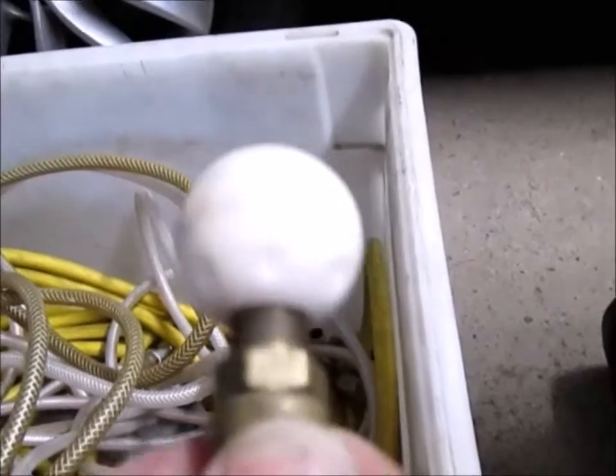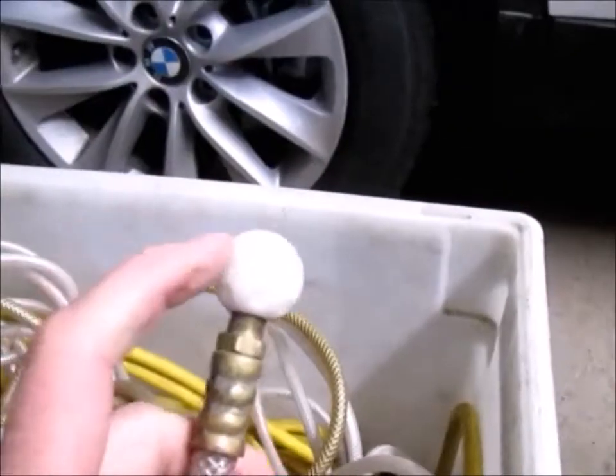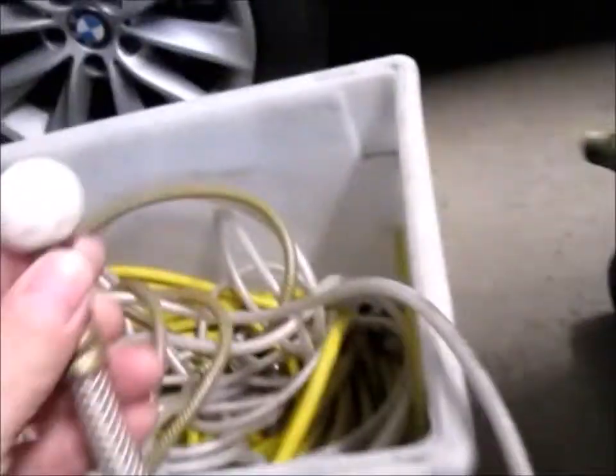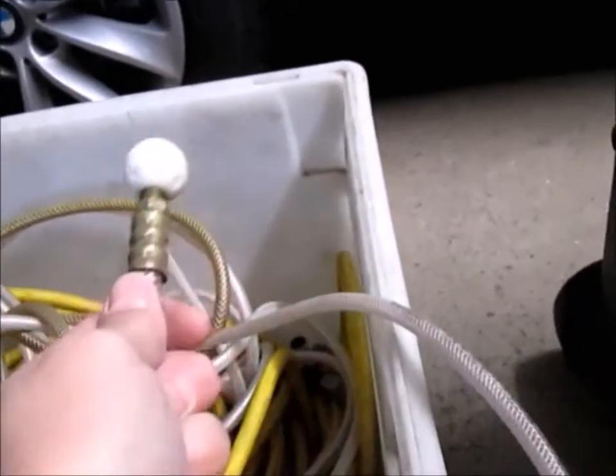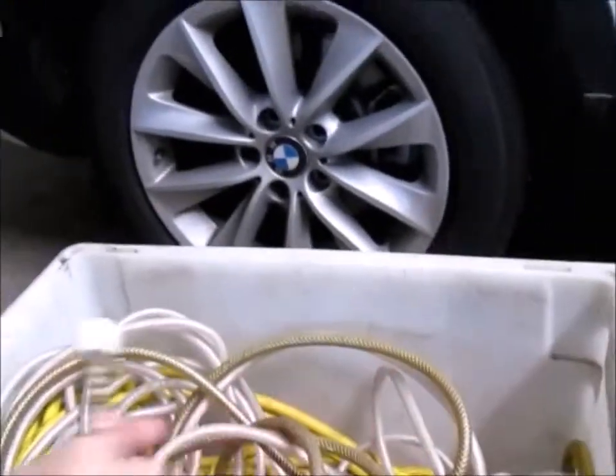Here's the end — we've got little circular balls. They've got holes on the back half, so as we push this in it's blowing air back toward me and pushing the ball down the ductwork. There's another ball where the air is on the front — one hole in the ball is offset to the side. As you're feeding it down and turning it back and forth, it'll cause the ball to weave from one side of the duct to the other, so if you've got a wide duct you can control the ball and have it go back and forth.